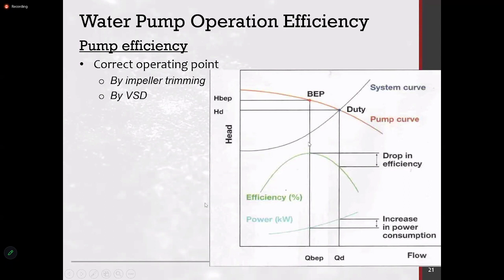Okay. So if you take the highest efficiency point here, which is the maximum efficiency, the pump should ideally operate here. But it's actually coinciding here, so it's actually operating here. So this is your duty point. Then your actual efficiency is here, so this is the drop of the efficiency. And if you take the power consumption, at the best efficiency point the power consumption is this, but the actual power consumption is here. So these are the three curves: the power curve, the efficiency curve, the pump curve, and the system curve.